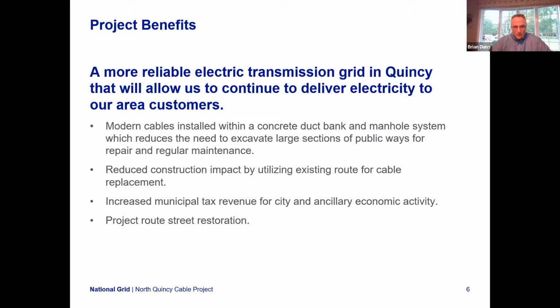Continuing with the benefits: the modern cables installed within a concrete duct bank and manhole system will reduce the need to excavate large sections of public ways for repair and maintenance. Currently, with the direct buried cables, it's a lot harder to find where the faults are or where dig-ins have happened. There's also a fluid within the cables that keeps them cooler and prevents overheating, and finding those leaks is difficult. With the duct bank system, it's a lot easier to trace things back, and it's just a lot safer as an encasement for the electrical conduits.